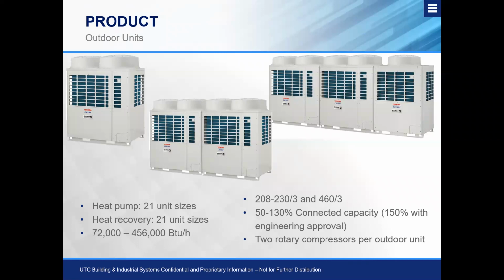Okay, a good rule of thumb, if you don't understand what connected capacity is: if we look at 50% capacity within the absolute minimum that we have connected, so we have a 6-ton outdoor unit and we only have 3 tons of indoor units connected to it, that would be 50% connected capacity. 100% connected capacity would be a 6-ton outdoor unit with 6 tons of indoor units.